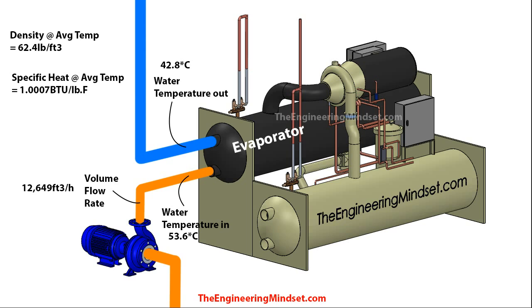Coming on to the imperial version — these values are actually from a real chiller operating at 100% maximum demand. The pump is providing water at 12,600 cubic feet per hour. The temperature of the water going in is 53.6 degrees Fahrenheit, and the water coming out is 42.8 degrees Fahrenheit. At the average temperature, the density of the water is 62.4 pounds per cubic foot, and the specific heat capacity is 1.0007 BTUs per pound per Fahrenheit.